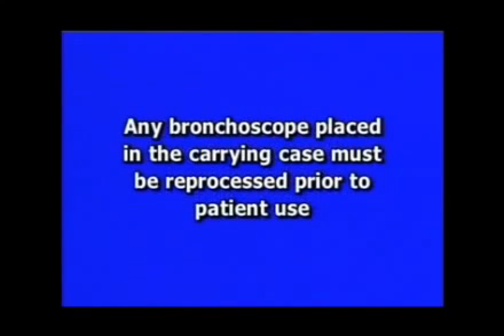A word of caution: do not use the bronchoscope's carrying case to store patient-ready equipment. Any bronchoscope placed in the carrying case must be reprocessed prior to use with another patient. Autoclavable bronchoscopes that have been steam sterilized should remain in their wrapped sterile tray until further use.